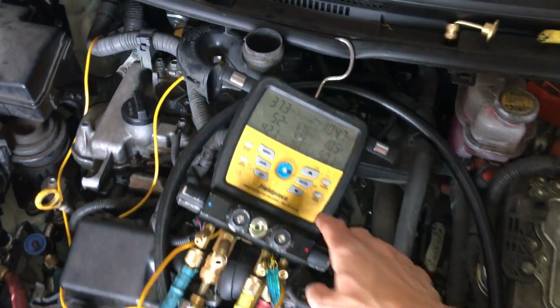So right now we're pretty steady at about 5 degrees superheat, and this is an expansion valve system. You go over to subcooling, we're at 10 degrees. But you'll also see this change depending on ambient and depending on what the computer is telling the compressor to do and everything it's doing.